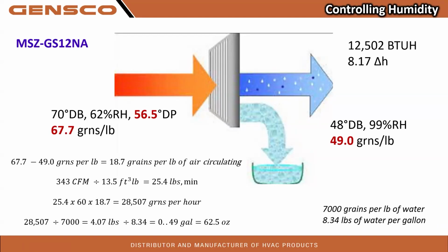67.7 grains per pound. And if we ran the unit with the same BTU output, we're going to end up with 49 grains. Again, we're over 18 grains per pound of air circulating. We're still removing pretty good water, 62 ounces if we could run for 1 hour. But with a 70-degree dry bulb, and that's what every unit operates off of, dry bulb, we're not going to run. So we're not going to get rid of this water, and that humidity is going to remain high. So this is where we run into a problem in the Northwest in our marine environment because we don't have a load. We can't keep the unit running long enough to actually remove water.